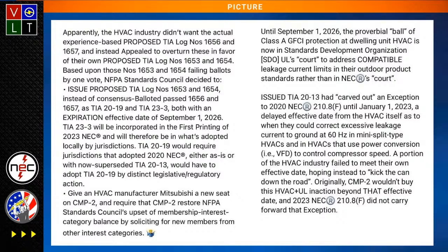That brings us right into the next part of this, because it says: until September 1st, 2026, the proverbial ball of Class A GFCI protection at dwelling unit HVAC is now in the Standards Development Organization, UL's court, to address compatible leakage current limits in their outdoor product standards, rather than the NEC's court.